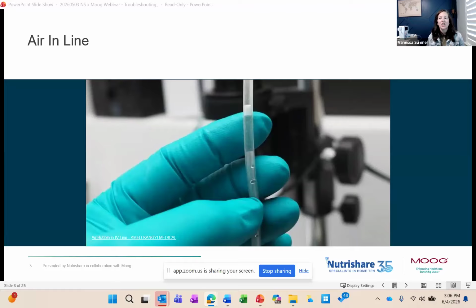One thing you may want to check, or ask your pharmacy about, is the air sensitivity setting on the pump, because you might not be able to avoid all of these air bubbles. But you can decrease the amount of air in line alarms you receive on your pump, especially if you're infusing at night.